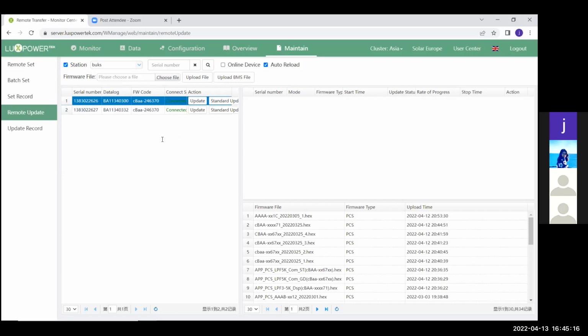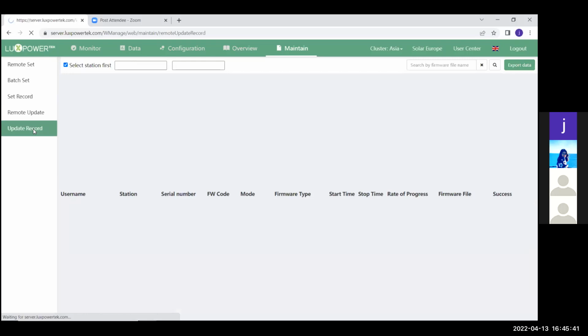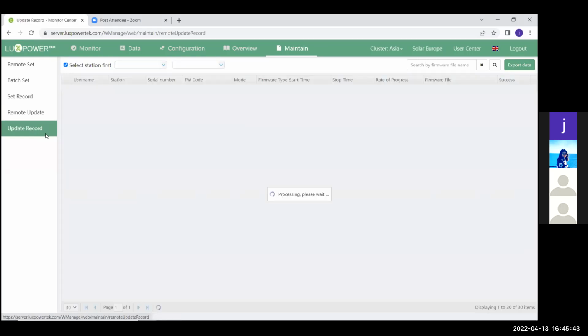Then if you have a parallel system, always make sure that the firmware code you see here is exactly the same. Otherwise, you'll have trouble in a parallel system. It won't communicate correctly and it won't do what you tell the system to do. So always update the parallel system to the newest firmware so that you know all your inverters are on the same firmware. From here on, you'll be able to see an update record if your updates have been done.